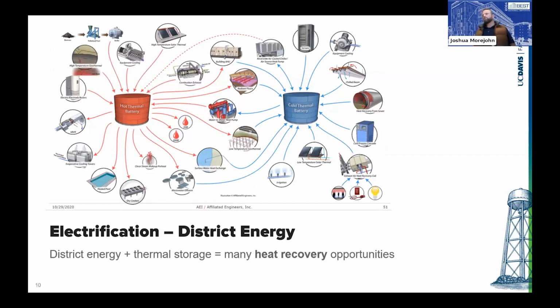This is our consultant put this together just as an illustration of all the opportunities. When we talk to people about converting from steam to hot water, a lot of people think it's not that much different. You know, what's the difference? Steam and hot water, it's a different temperature, but that temperature is important. And at the lower temperature, our hot water design temperature right now is 160 degrees Fahrenheit.